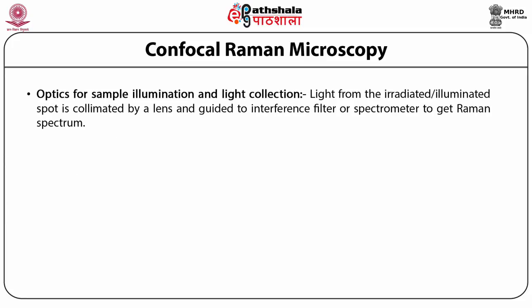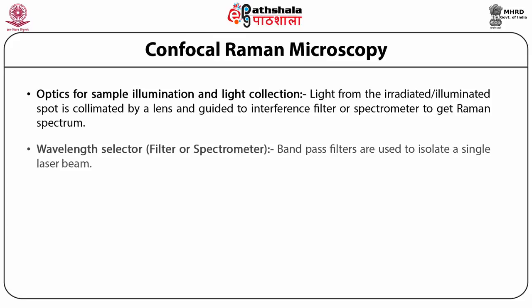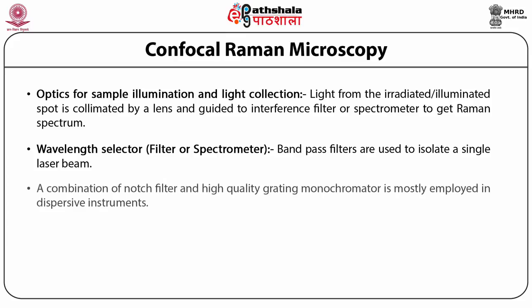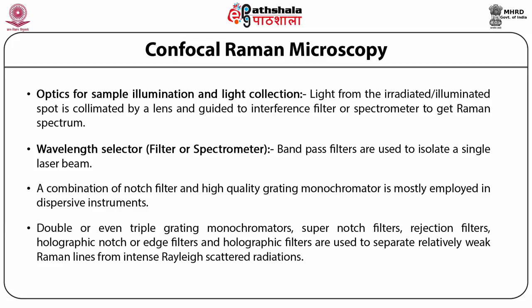The second component is optics for sample illumination and light collection. Light from the irradiated spot is collimated by a lens and guided to an interference filter or spectrometer to obtain a spectrum. Third is the wavelength selector — filter or spectrometer. Bandpass filters are used to isolate a single laser beam. A combination of notch filter and high-quality grating monochromator is mostly employed in dispersive instruments. Double or triple grating monochromators, super notch filters, rejection filters, holographic notch or edge filters, and holographic filters are used to separate relatively weak Raman lines from intense Rayleigh scattered radiation.